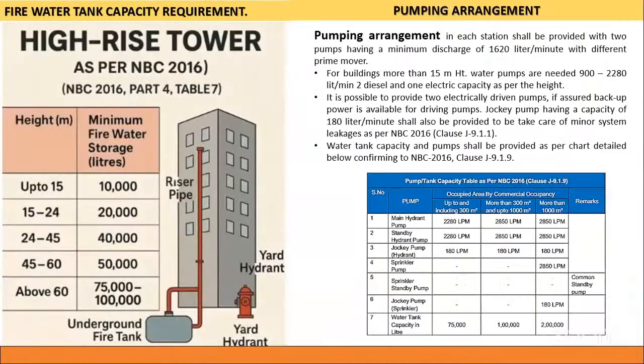We always plan for the mandatory requirements of fire tanks to be provided. It is dependent upon the height of the building and occupants. Up to 15 meters, we should go for at least 10,000 liters of fire storage tanks. And in increasing order, for a building above 60 meters in height, we should go for 75,000 or 1 lakh liters of tank.